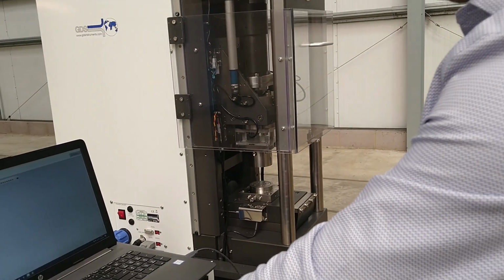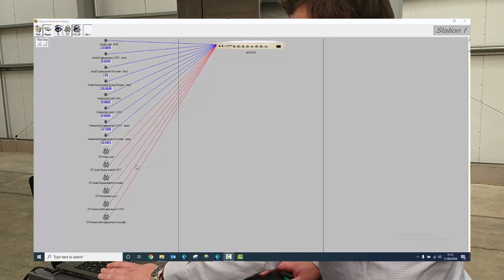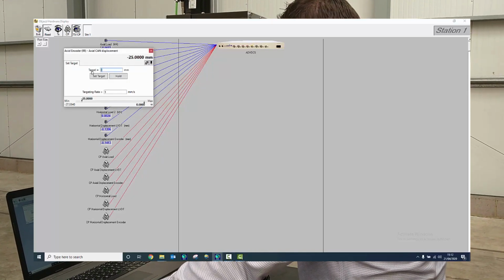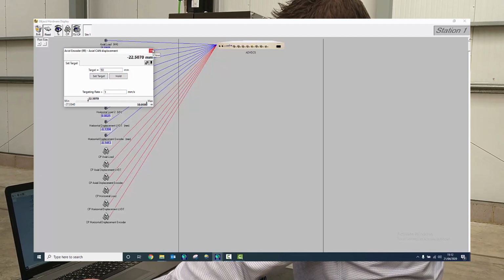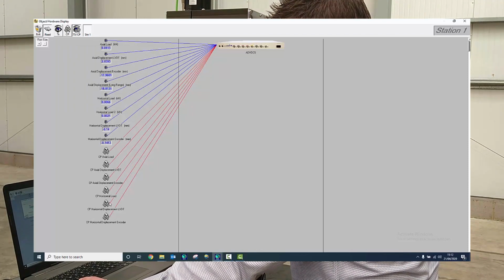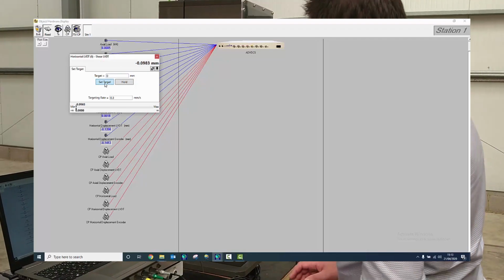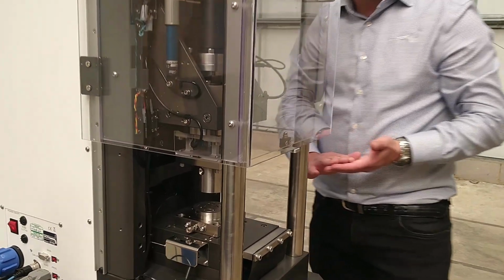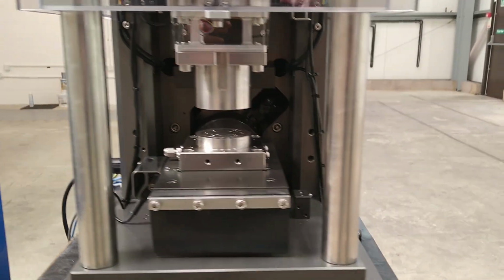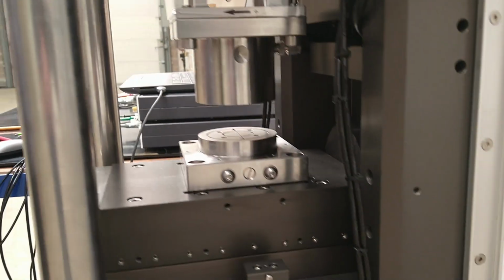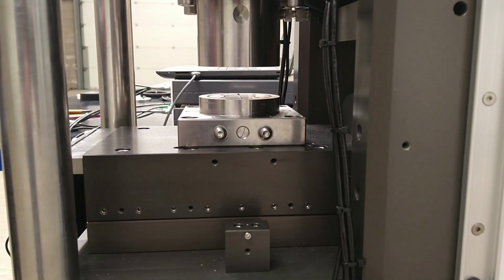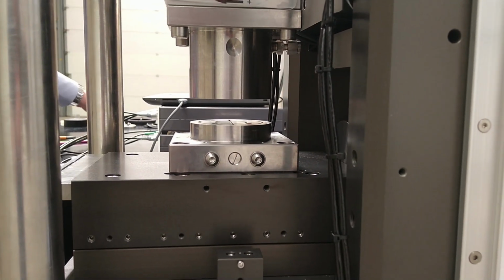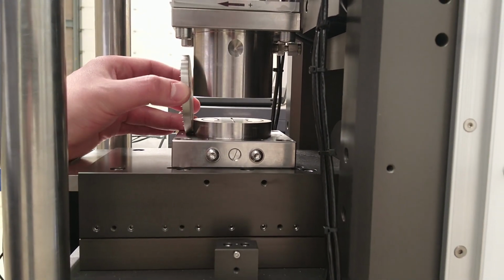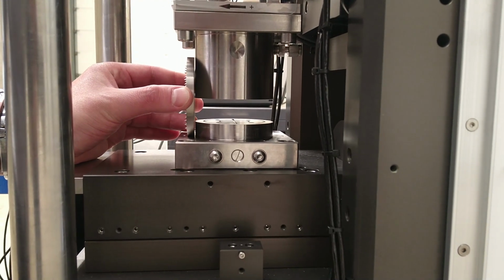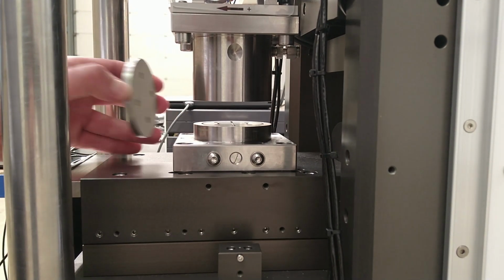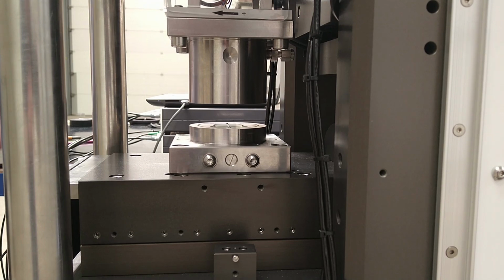And from the software, from the object display, we can go to axial encoder and target the maximum positive position to bring the top cap and the pedestal closer, and then using the horizontal LVDT we target 0 position, which should make the top cap and the pedestal in line and two faces parallel. That's what you're looking for, is for that face over here to be in line. I'm just gonna quickly use one of the discs. So you can see both the top cap and the pedestal are in line.